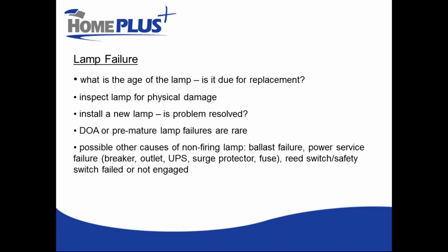So what a lot of these systems are designed to do is to prevent a lamp from firing when it's not inside its chamber. If you had a UV system from 20 years ago, or even from what's considered a mainstream manufacturer today, or some of the real low end stuff on the market that's still out there, it's possible to plug a lamp into the lamp harness, plug the system into power, and sit and stare directly at that UV lamp and destroy your eyeballs.